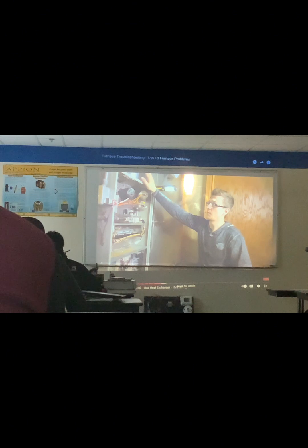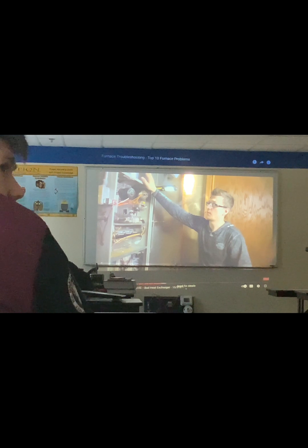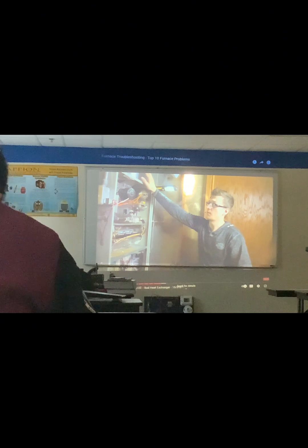Deal's off. I'm not touching it. I'm gonna shut the gas off. I'm gonna clip the red wire. Roll it back, because you're not gonna say I came there and did it. I'm gonna write you an invoice that says this furnace needs to be replaced. You're gonna sign it: do not run or operate this equipment. It is unsafe and dangerous and could cause harm or death. You write that on there.